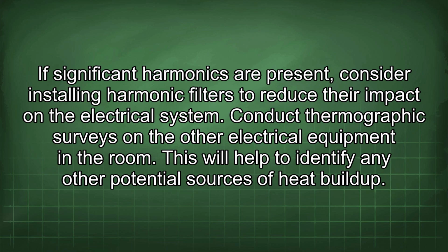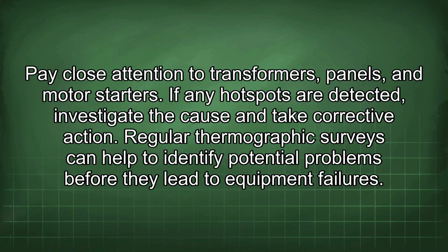Conduct thermographic surveys on the other electrical equipment in the room. This will help to identify any other potential sources of heat buildup. Pay close attention to transformers, panels, and motor starters. If any hotspots are detected, investigate the cause and take corrective action. Regular thermographic surveys can help to identify potential problems before they lead to equipment failures.